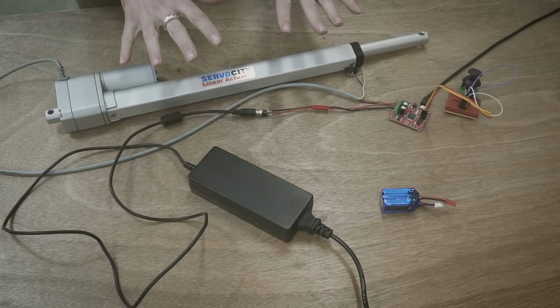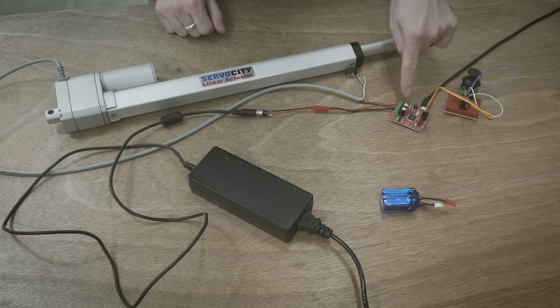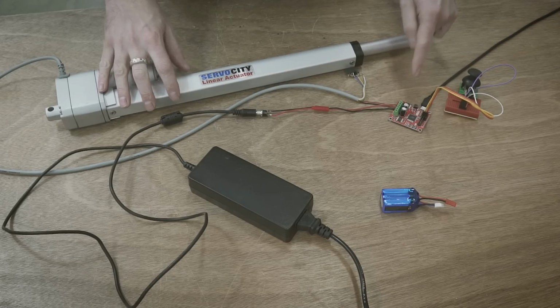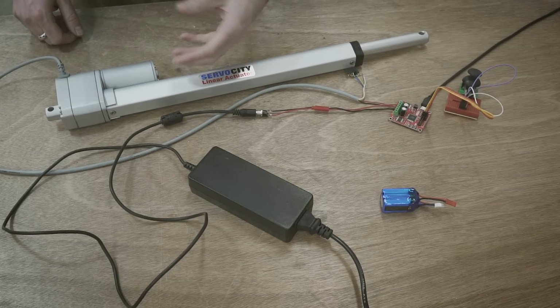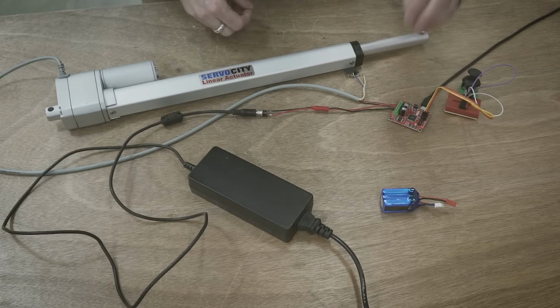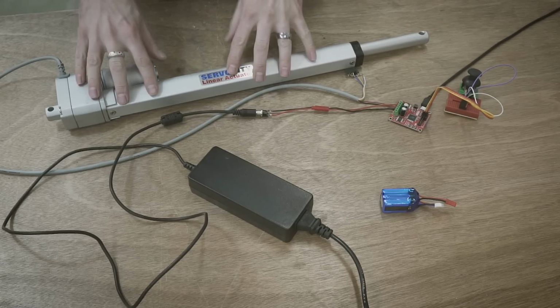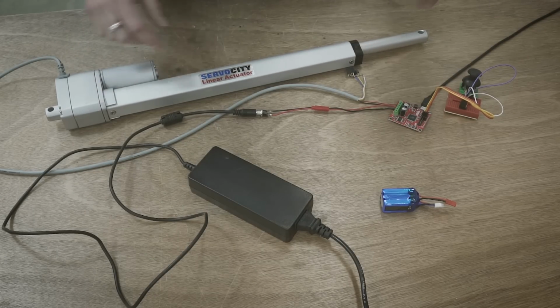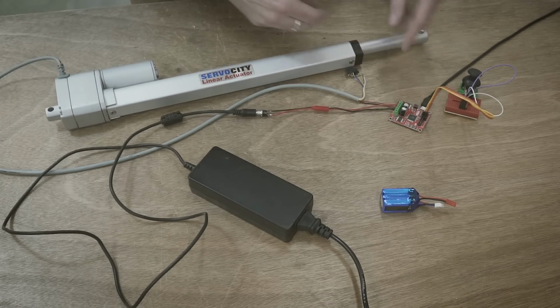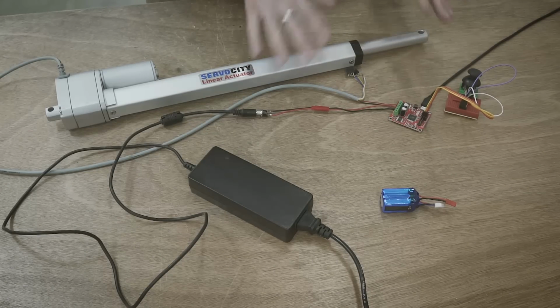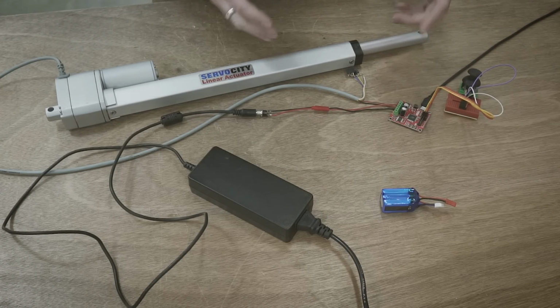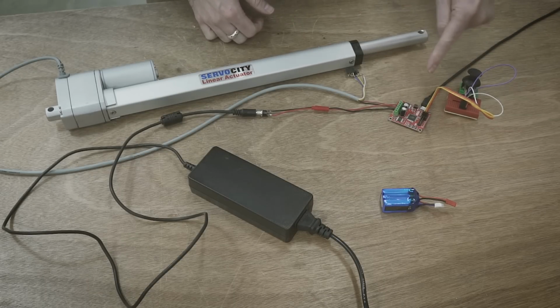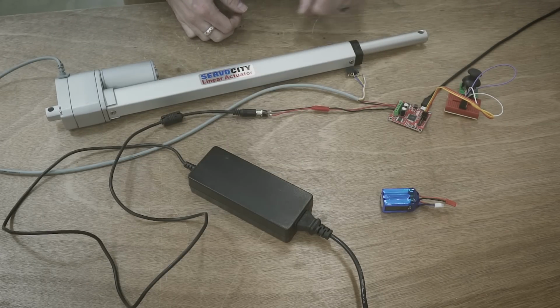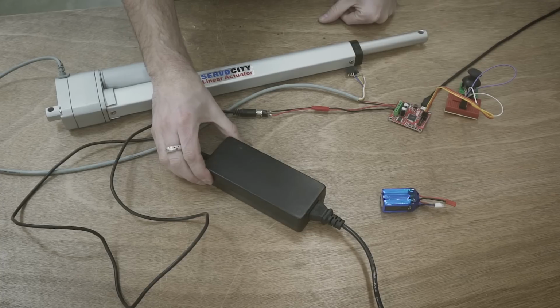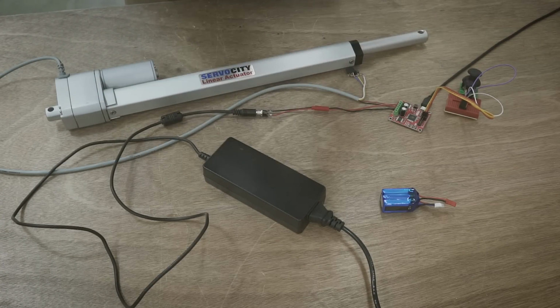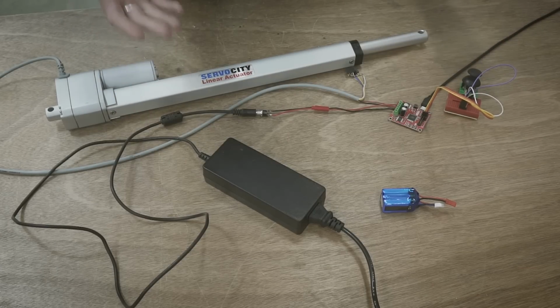So what's happening here is this is a regenerative braking motor controller. That means that this motor spins and it has some inertia, and when it slows down and stops, this is no longer pushing power into the motor, and therefore the motor inertia is backfeeding back into the motor controller. This is pretty standard. This motor controller, instead of clamping that power down, is backfeeding it back into the power supply, and the switch mode power supply really doesn't like power coming back into it, so it is turning off and the whole system turns off.